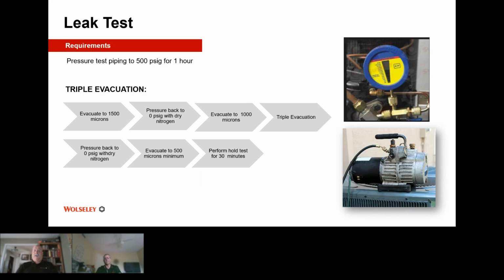Once we've reached 1,000 microns, we are going to stop the vacuum pump, and we are going to inject nitrogen again, back up to 0 psi gauge pressure. Then once we reach 0, we are going to once again turn the evac pump back on and go down to 500 microns. Once it reaches 500 microns, we are now going to perform a hold test. With this hold test, we want to make sure that the pressure stays around 500 microns. If it holds for 30 minutes, we have made sure that the unit is in a complete vacuum and that we are good to go to start commissioning and start up the unit.